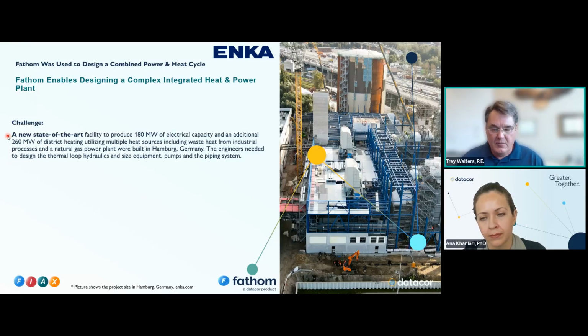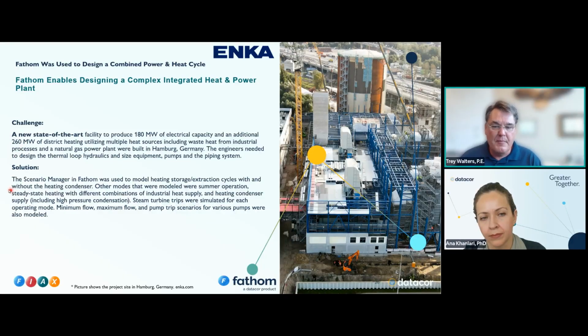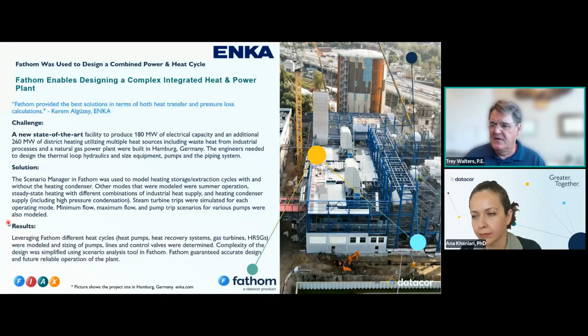Engineers needed to design the thermal loop, hydraulics, and size equipment, pumps and the piping system. They used a scenario manager in Fathom to model heating storage, extraction cycles, with and without the heating condenser. Other modes, they had to look at summer operation, they had to look at winter operation, what the industrial heat supply is, whether the heating condenser supply, steam turbine trips were simulated, minimum, maximum flow, pump trips. So they had a whole bunch. And if I remember, there was like 17, and we might say that in here. I think there's about 17 different scenarios.